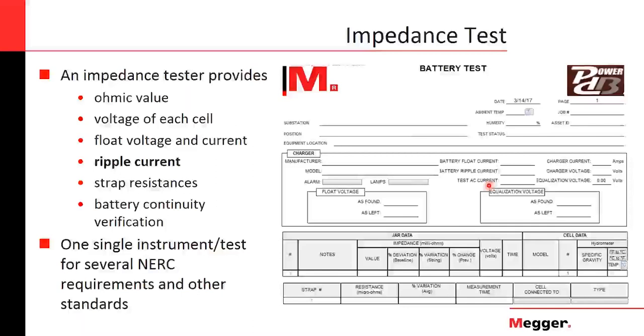The maximum recommended ripple voltage is 3.5% of the RMS voltage, and the maximum recommended ripple current is 5% of the 8-hour rate discharge of the battery. So exceeding these limits can lead to a generalized elevated temperature in the batteries, and temperature is one of the worst enemies of batteries. So watching out for ripple current is very, very important, and you can trend this value as well when you perform an impedance test.